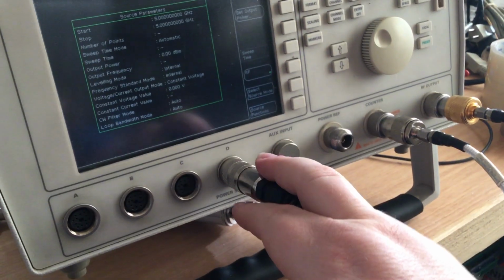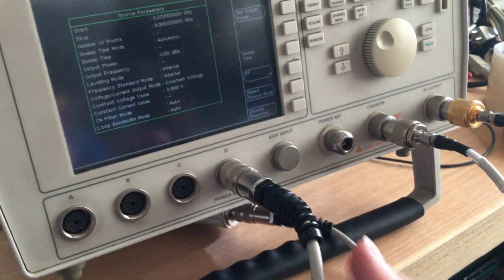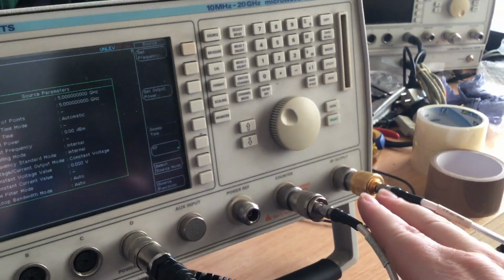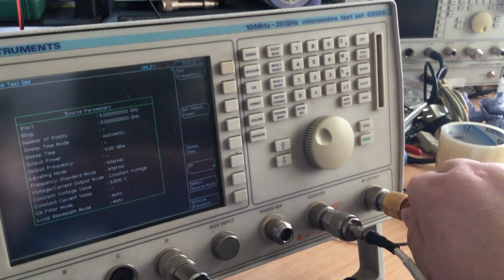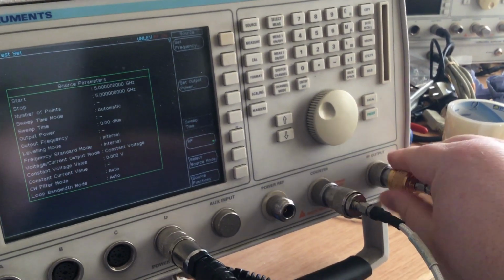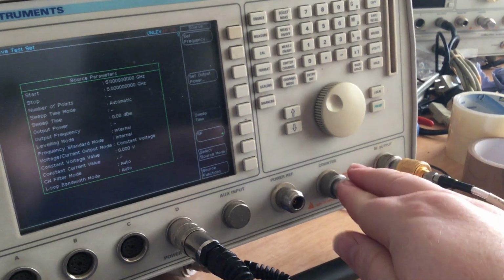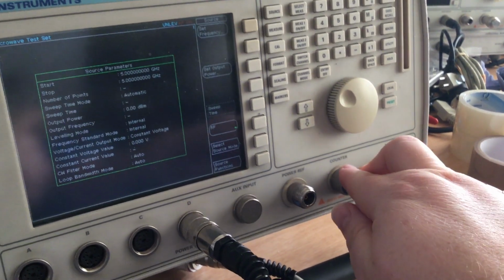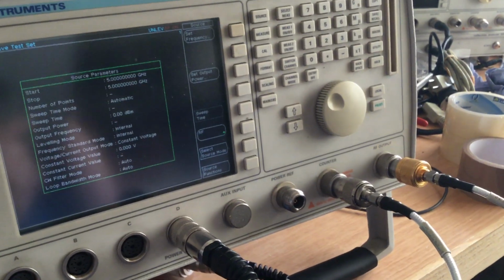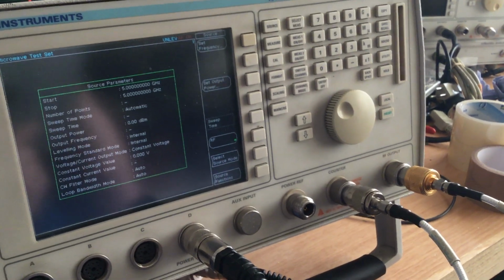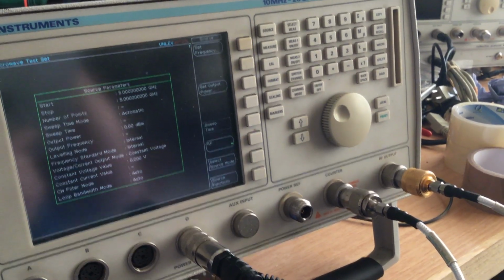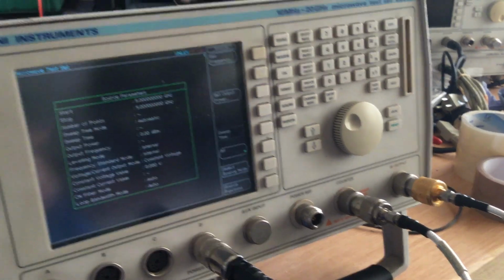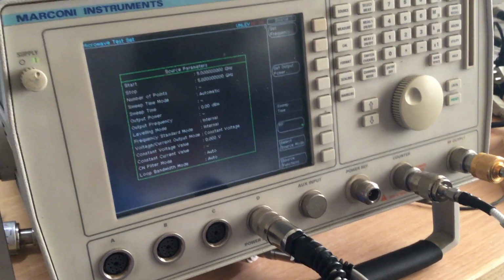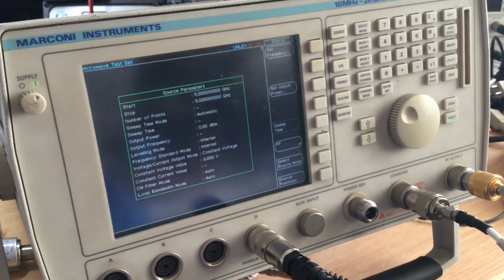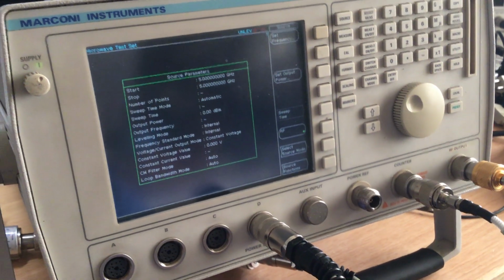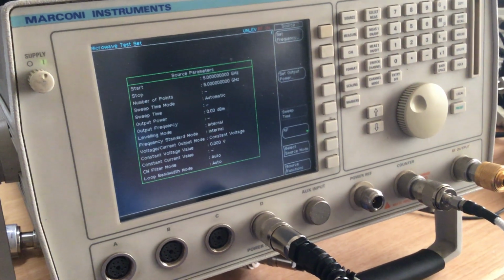We've got a power sensor connected to port D, which we're going to calibrate in a moment. We've got a spectrum analyzer connected to the output of the RF here, the RF signal output. We have a signal coming in from another signal generator to the counter, so we can check the frequency counter operation as well. And then we'll go into the service mode and then to instrument calibrations mode and show you that, so that you can follow my diagnostics and ultimately to calibration.